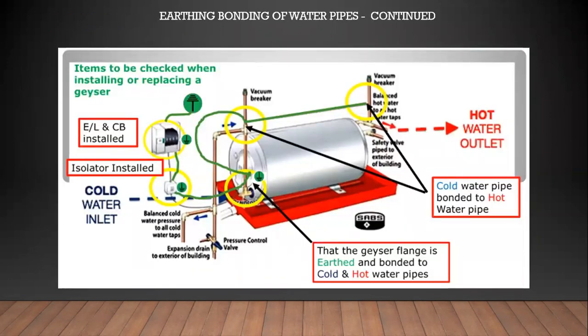Earthing wires of bonding connectors. I've got a nice drawing there that I actually show you. Your hot and cold water pipe must be bonded together. The earth stud or terminal onto the geyser body itself must be bonded, and that must go to your distribution board with a minimum of 2.5 millimeter square earth wire.